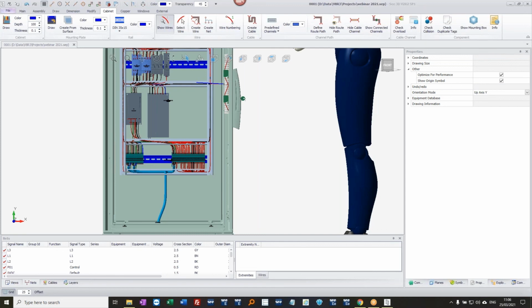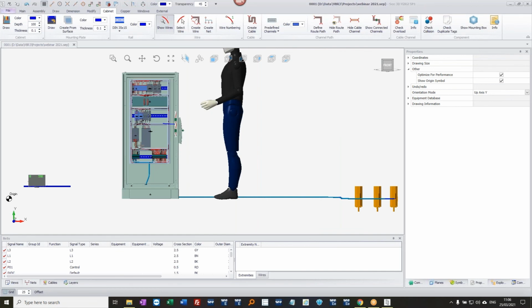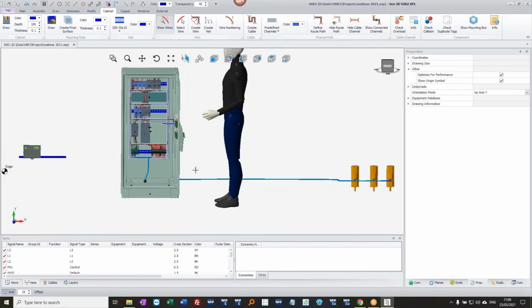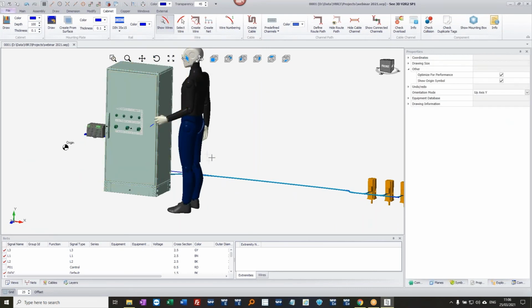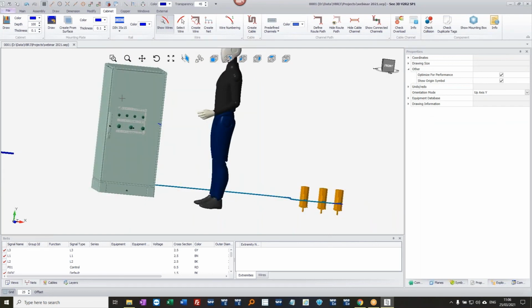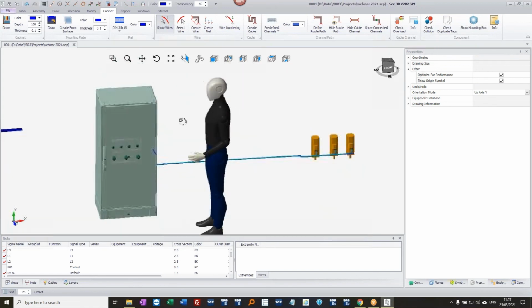A couple of questions, really. I think I've seen this before, but if you had an isolator on a back plate and a handle on a door, can you make those up and put the punchings on the door? Yeah, absolutely. You would have to have the door closed. And if I just drop it back into position onto there, you'd make up the component in the background, and it has a snap point on the back. And then the shaft and the handle are a separate object, which you then bring in and it snaps into position on the door. Because it's important, it's two parts, because you've got two different mountings. You've got a mounting on the door and a mounting on the actual back of it, in the shaft, basically. So it has to be two separate items. You can't bring it in as a component with the shaft and the item for the door.